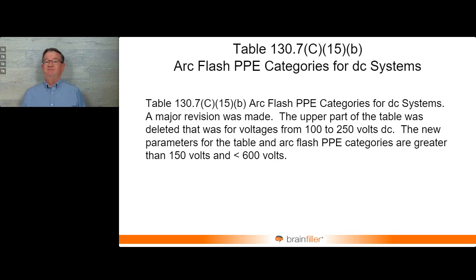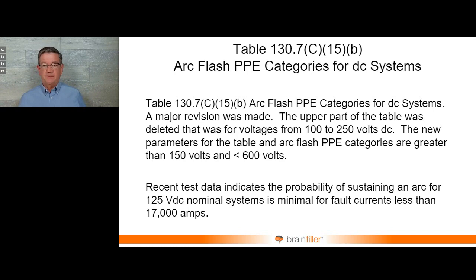DC arc flash. We're learning more about DC arc flash, but there's still a long way to go. And there's tables within NFPA 70E about PPE for DC arc flash, and they now and then get revised, and this is one of those times that the tables for DC arc flash for selecting PPE, there's been some new test data that says it's pretty hard to sustain an arc below 125 volts DC for fault currents less than 17,000 amps. So the voltage, to sustain an arc over a greater distance, you need a greater voltage.